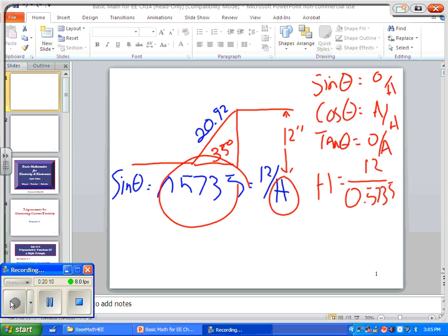So anyway, this is how we would do an offset where we can't use what's called a standard multiplier. A standard multiplier is like if you're going to kick up 30 degrees, whatever the obstruction is, you go twice that. Very handy multiplier, right? But we won't get into that. So then the sine, cosine, tangent is used in circuits. Let's get a new slide.